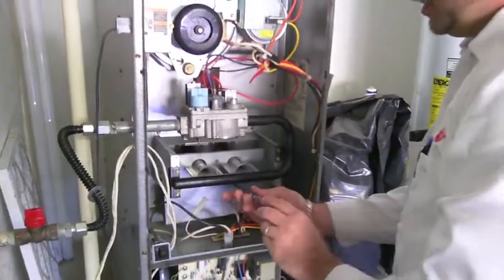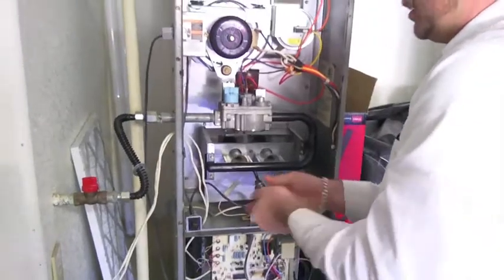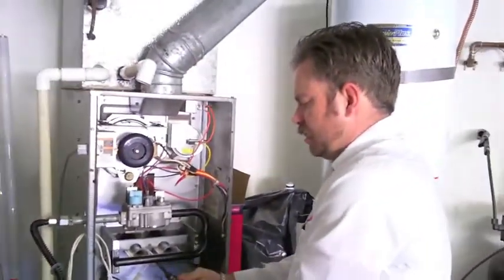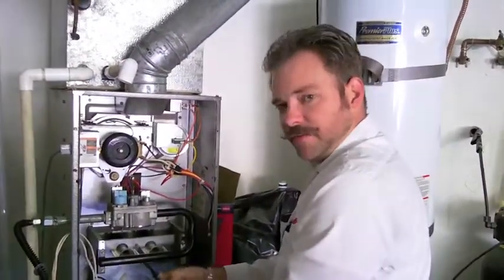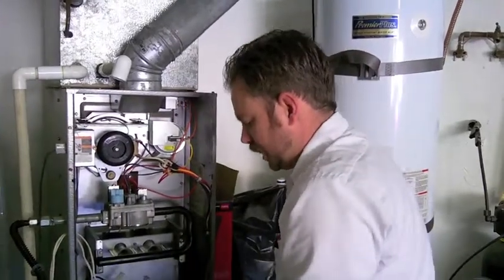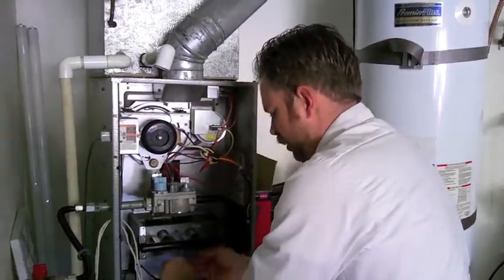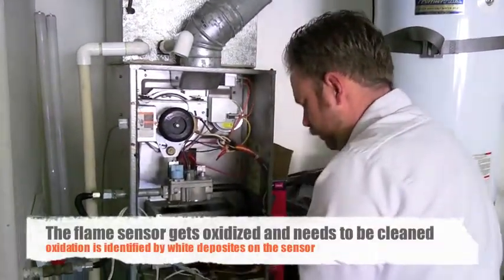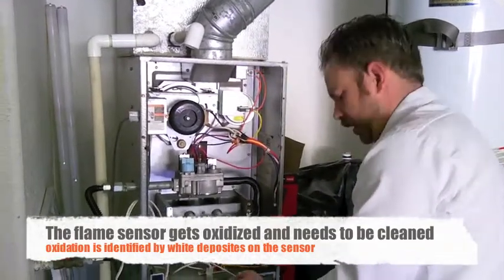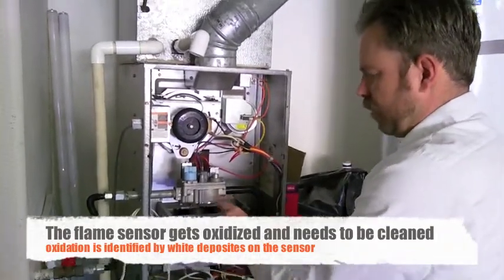Clean off the flame sensor. And this is a flame proving sensor, which basically means that it tells the circuit board that the flame is lit. So when the gases turn on, if the flame is not lit, it'll actually take the gas or the valve off.